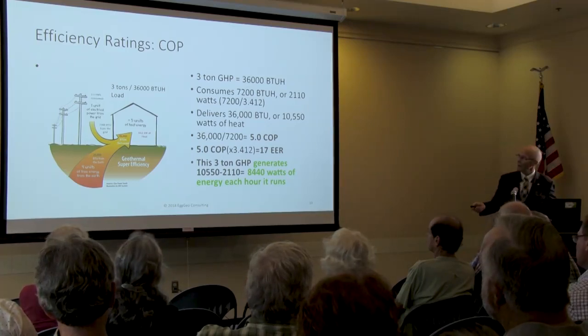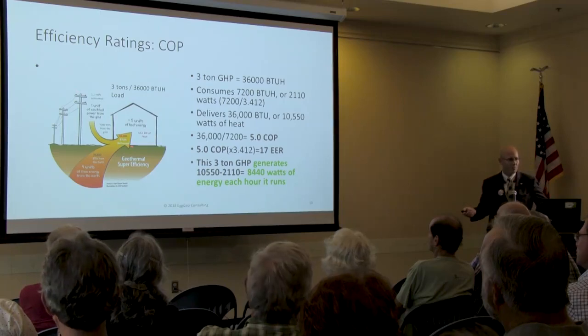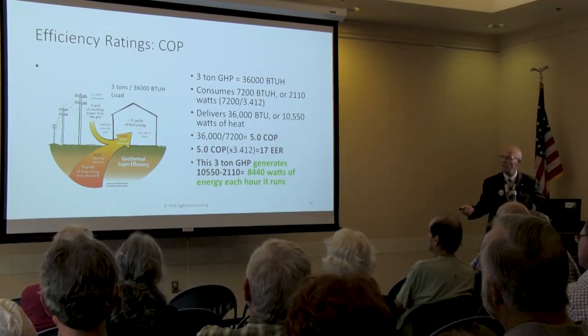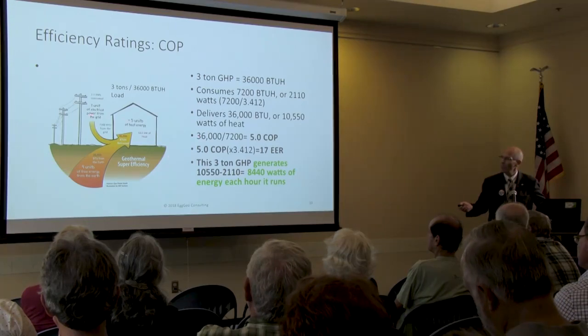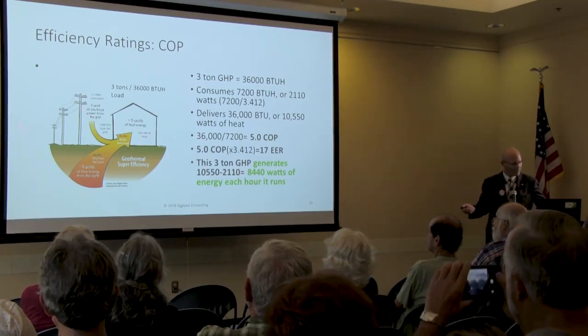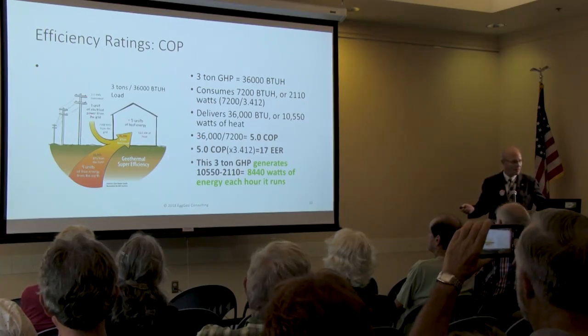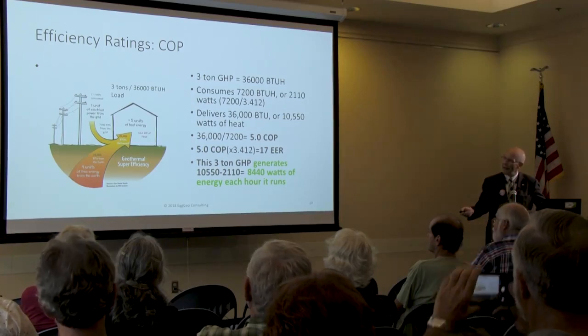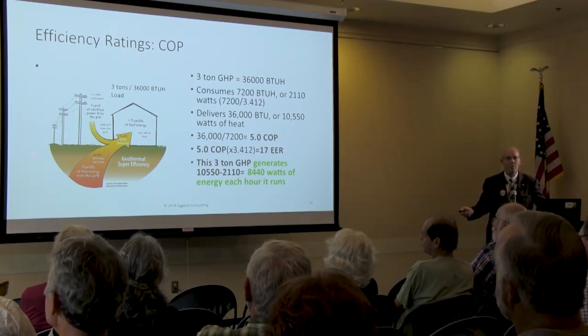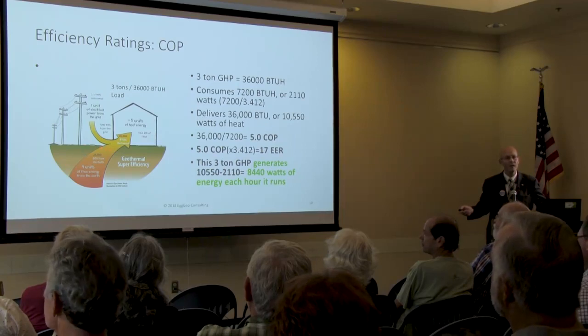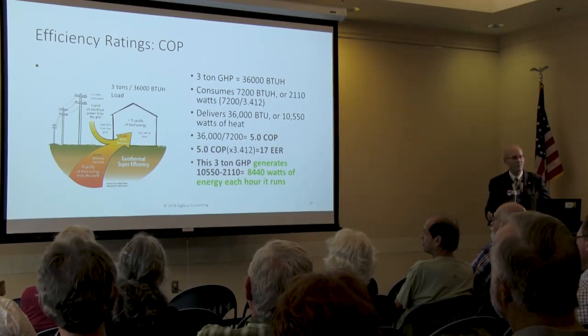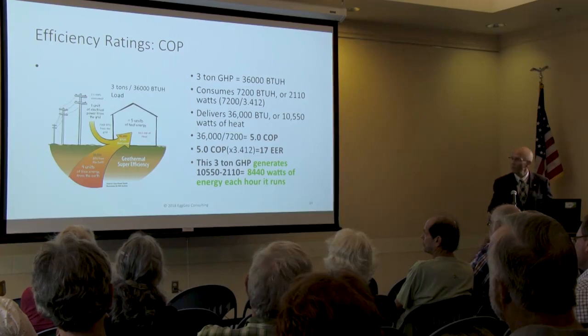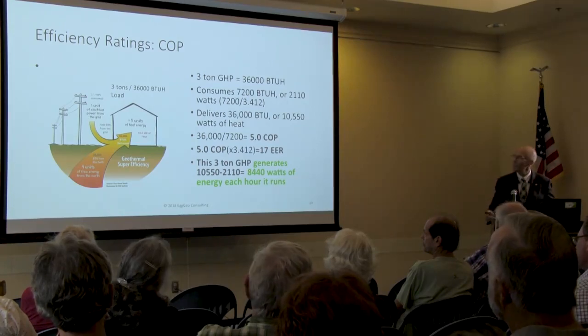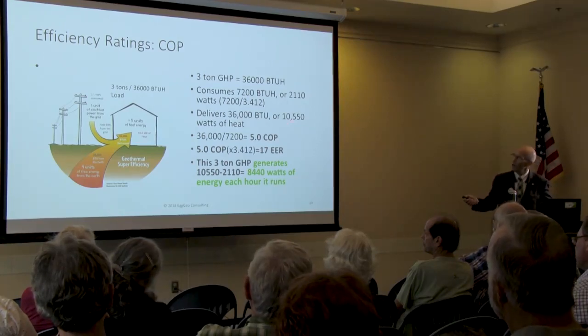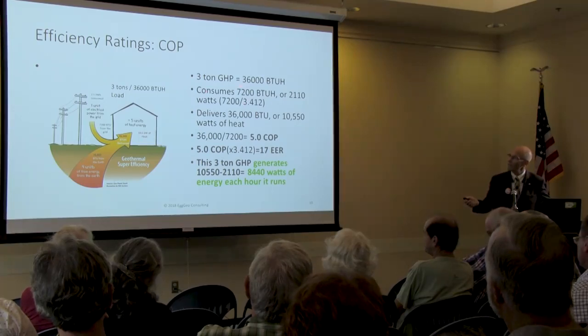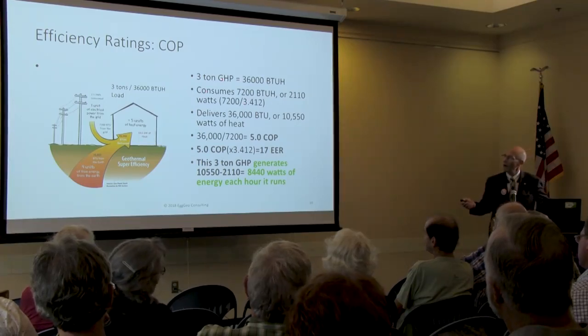Here's a great example, and I love this image because it is one of the best images for showing what a heat pump does. I take 1 unit of electricity from the electric grid, and with that I use a heat pump to pump 4 additional units of heat from the ground for a grand total of 5 units of heating in the building. That gives me a COP of 5. Here is all of the calculations that you need to understand that.